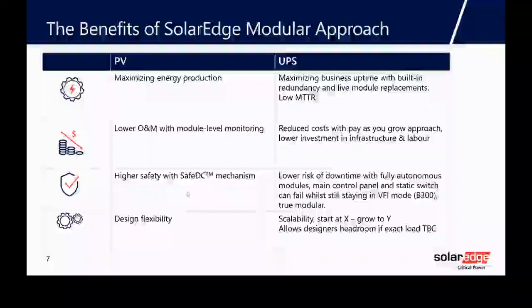In the world of UPS, being modular increases your uptime. If one of the power modules fails, it's not a disaster. The whole machine doesn't shut down; it just carries on because you have redundancy built into the system, and very low MTTR, mean time to repair. You can just swap these modules in seconds.